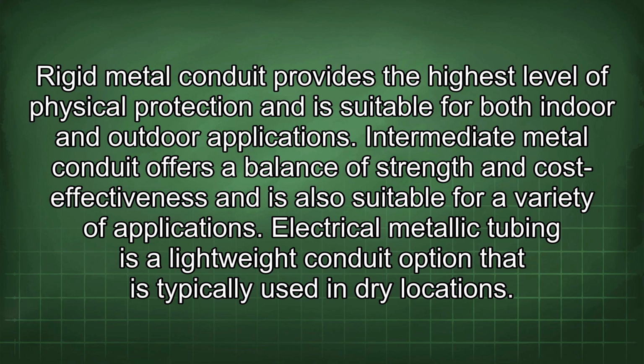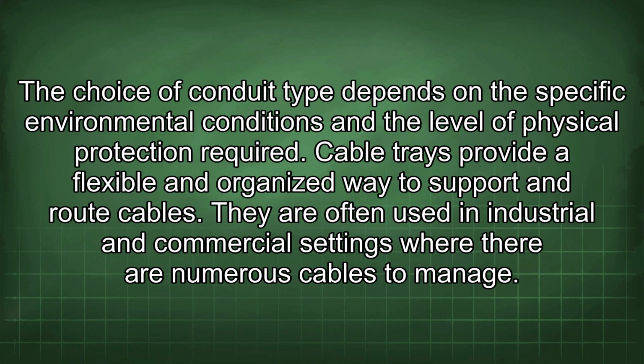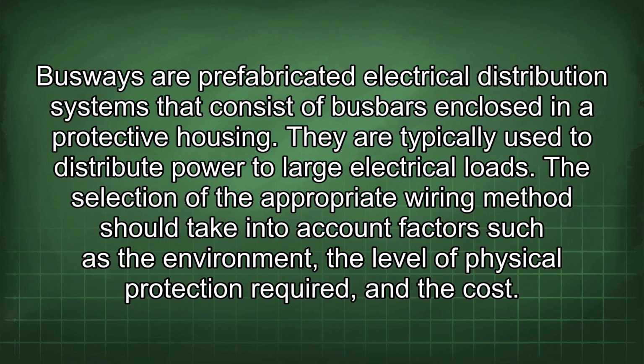Intermediate metal conduit offers a balance of strength and cost-effectiveness and is also suitable for a variety of applications. Electrical metallic tubing is a lightweight conduit option that is typically used in dry locations. The choice of conduit type depends on the specific environmental conditions and the level of physical protection required. Cable trays provide a flexible and organized way to support and route cables. They are often used in industrial and commercial settings where there are numerous cables to manage. Busways are prefabricated electrical distribution systems that consist of busbars enclosed in a protective housing. They are typically used to distribute power to large electrical loads.